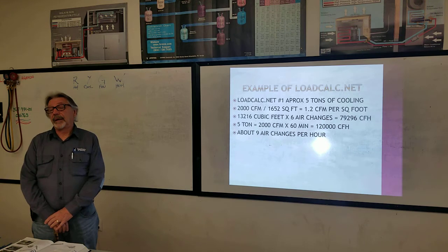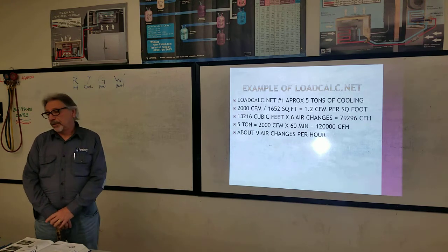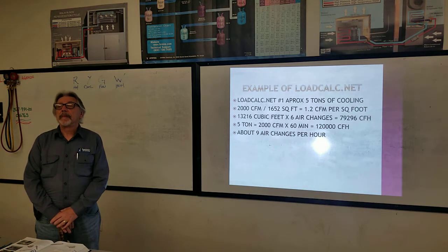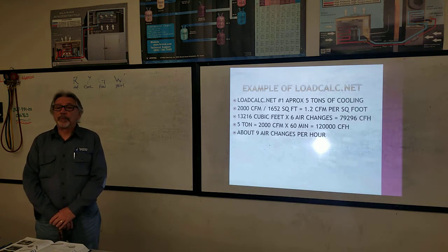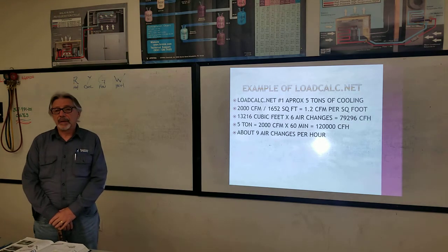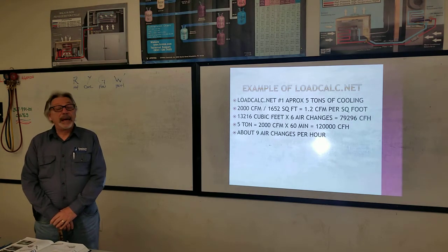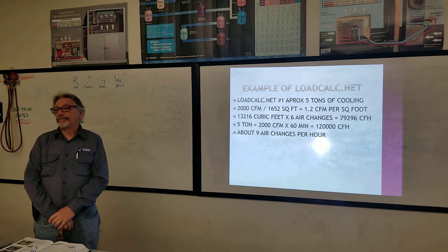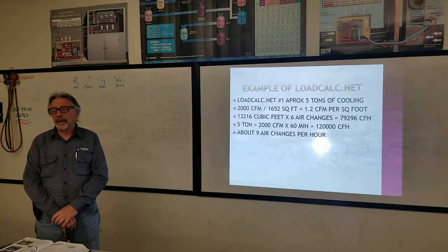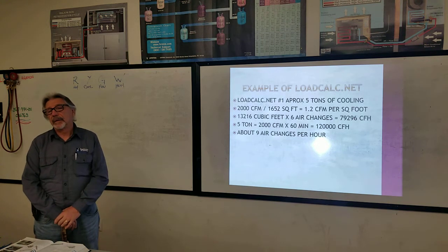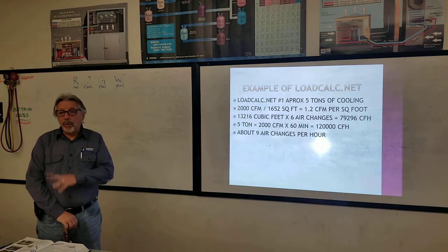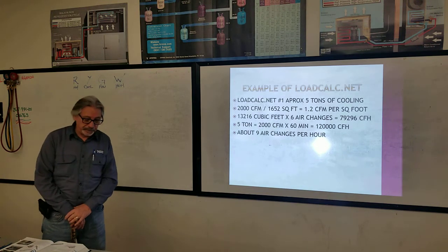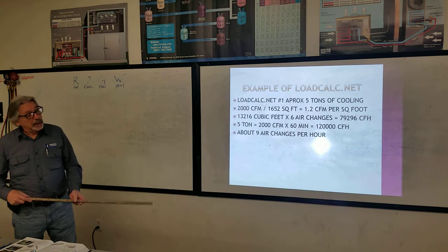We had an instructor I was talking to in Reading, and they were saying they were building apartments that weren't meeting the air changes per hour, and they were having problems with high humidity, not enough air movement, stagnant air, mold, stuff like that, in the new construction.